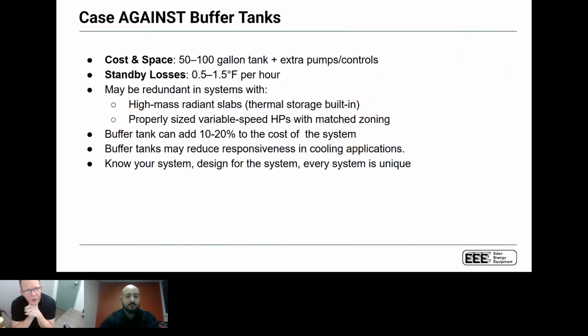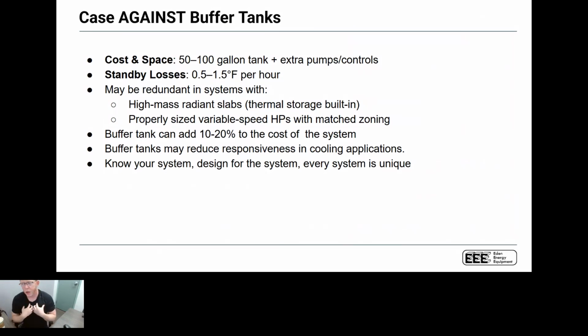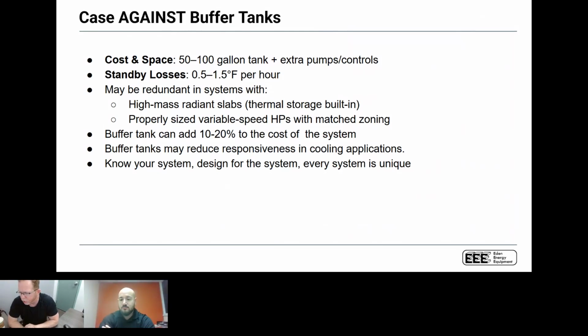Yeah, so I have an air-to-water heat pump in my house, and I use Jaga low-temperature emitters because of the temperatures and humidities in my house, which leaks like a cheese grater, would be the technical term for it. I get more comfort from using Jaga units. But the reality is, if you have somebody complaining about comfort in the space, it very likely is a control issue. Specifically, they probably have a water temperature that's not low enough to actually remove the latent energy. And my guess would be that they're trying to keep it above a dew point, but having a strategy for controlling sensible and latent cooling would be critical to how you control the cooling in that space and making sure it's comfortable. Like I can reduce the air temperature in my own home, but if the humidity remains elevated, I'm still going to be incredibly uncomfortable.